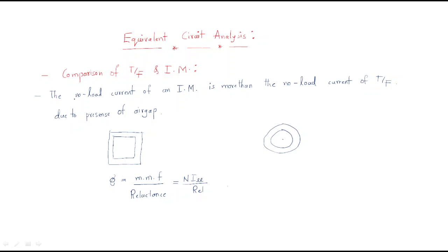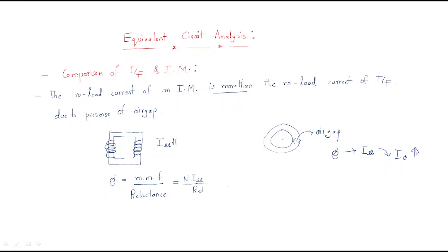The no-load current of the induction motor is more than the no-load current of the transformer, due to the presence of an air gap. Here, this is the stator, this is the rotor, and here we have the air gap. Through the air gap, flux is transferred from stator to rotor, which requires more no-load current. The magnetizing current is produced from the no-load current, so it requires more no-load current. In the case of a transformer, there is no air gap, so it requires less magnetizing current and less no-load current.